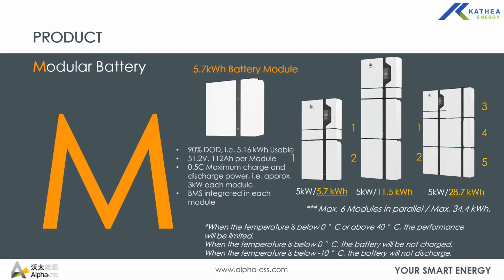And then the second aspect is the modular battery. The battery that we distribute our Alpha with is a 5.7 kilowatt hour battery, which has a 90% depth of discharge. So you can drain it down to its deeper levels of 90%. However, if push comes to shove, the battery can go up to 96%. But with the inbuilt BMS, it will always make sure it stops discharging at 90% whenever there is an alternative power source. So the 90% of 5.7, that's around 5.16 usable.